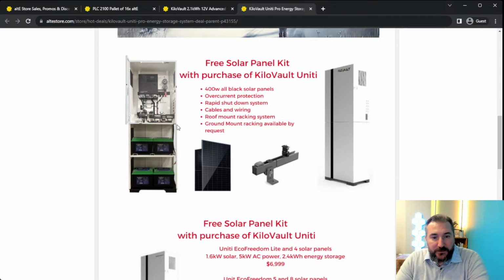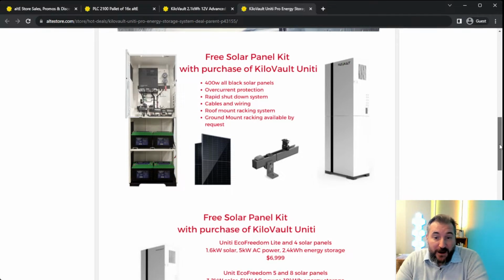It'll take maybe half an hour at most to put all the batteries in. You pop them into the battery-to-inverter cables, put them in, and it's all wired up to the bus bar, and your inverter is fired up. If you have your solar kit, you just put your solar panels on the roof and bring them into the labeled solar input section here. Super easy. It also has 5 AC breakers already built in, so you can use this as your AC load center, or connect it to a normal AC load center like your power panels.